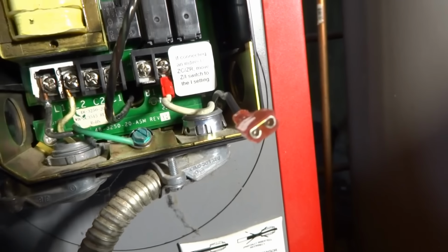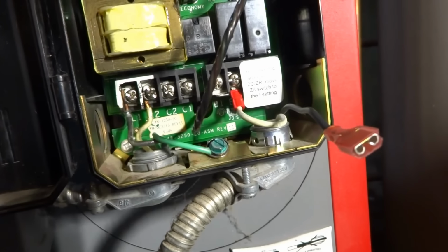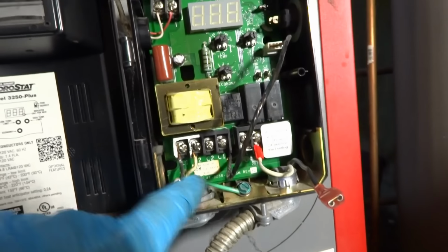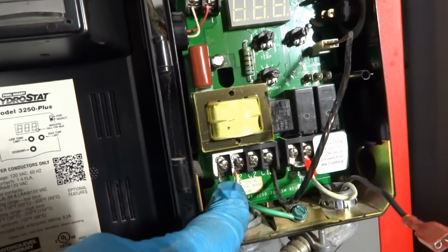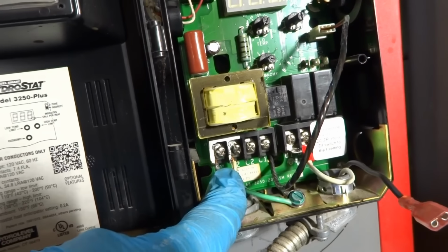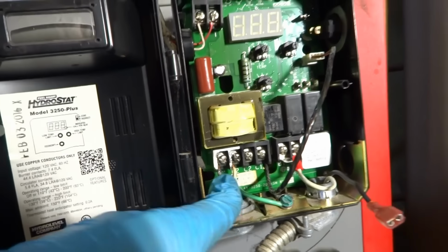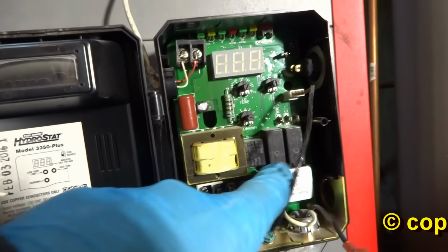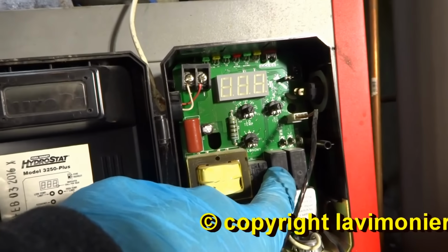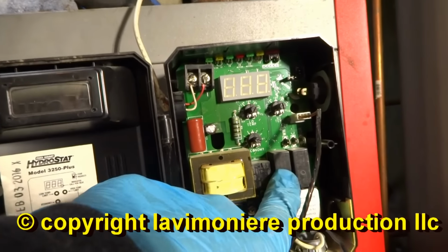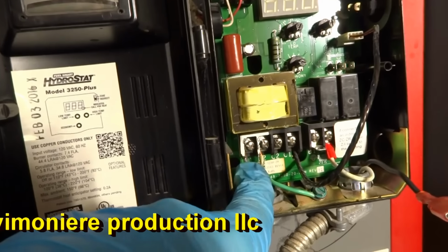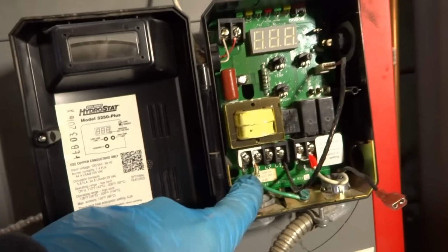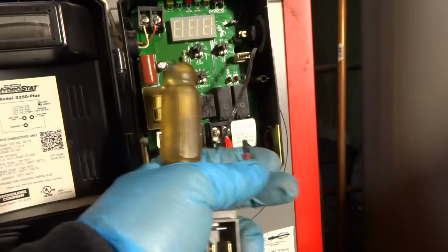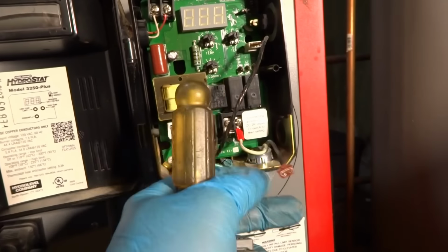That's fucking weird. This thing ran good for a long time. Let me pull this off here, and then we'll try it again. If it trips, we know it's in this control somewhere. It might be in one of these relays that it's not acting up until it clicks in. So let me disconnect this, and then we'll turn it back on. If the breaker stays on, we know it's got to be in this control because we've got the burner disconnected, right? Yep.